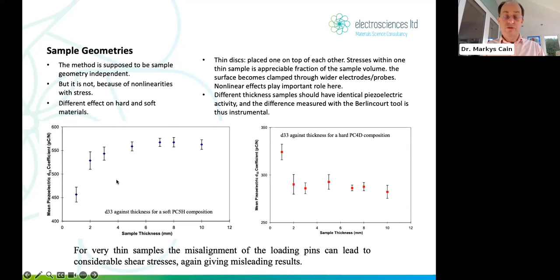You can get this. And you can see that once you reach something like a reasonable aspect ratio of maybe 4:1 or something like that, you end up with a fairly flat, non-changing value in mean effective piezo coefficient for soft and hard materials. But down here, down at the low sample thickness, you're clearly getting some material geometry related non-linearities, okay? And this is an issue, okay? Because the Berlincourt tool is meant to be geometry independent, but it's clearly not. The issue here is an instrumental issue.